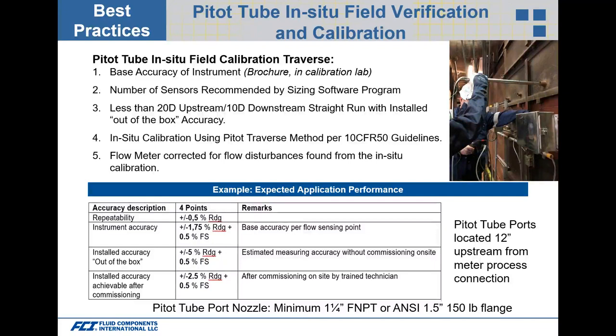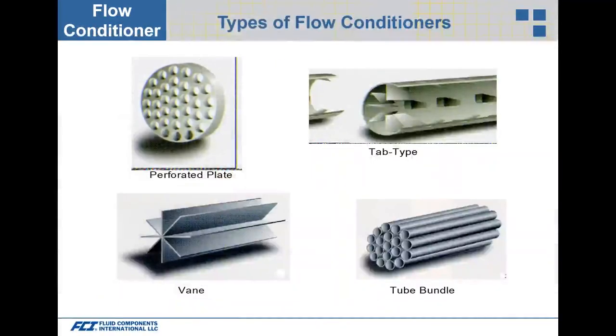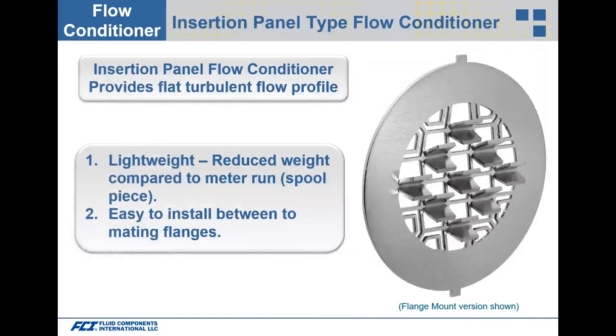Not only does the pitot tube traverse correct the installed accuracy, but it also uses a third-party meter to confirm the flow meter's accuracy. Gas flow conditioning is another option for smaller pipe diameters — 18 inch and smaller — using perforated plates, tab types, tube bundles, or vanes. An insertion panel flow conditioner creates a flat turbulent flow profile downstream of the conditioner. If the meter is calibrated through this flat turbulent profile at the factory and the same setup is used in the application, the flow profile will always be consistent and accurate.